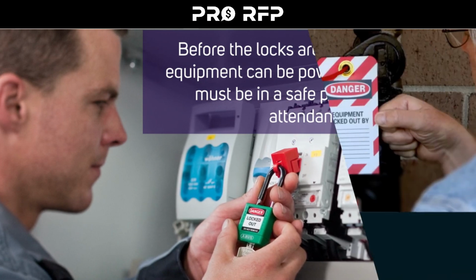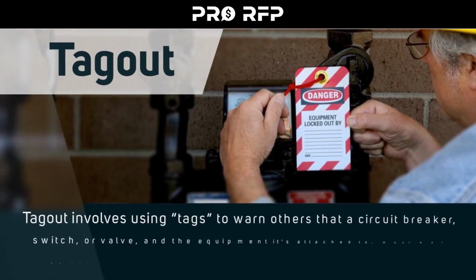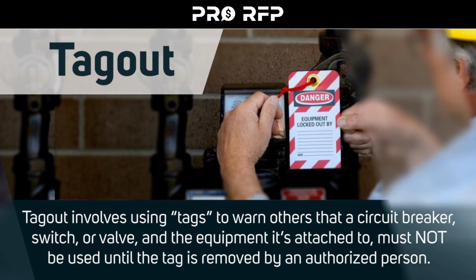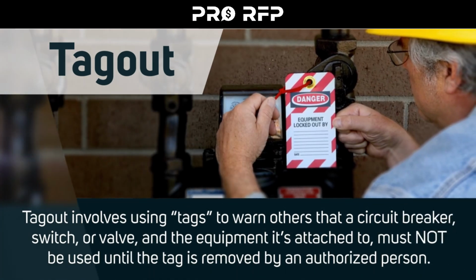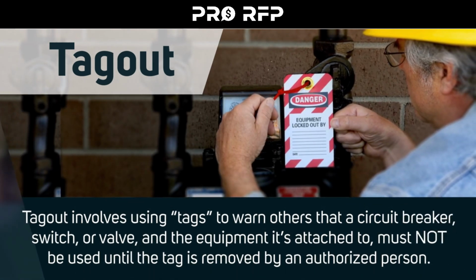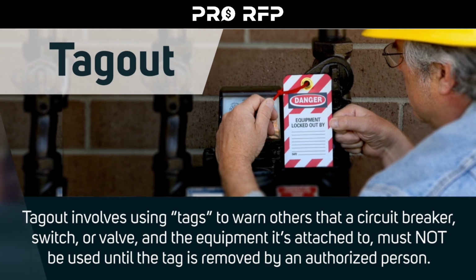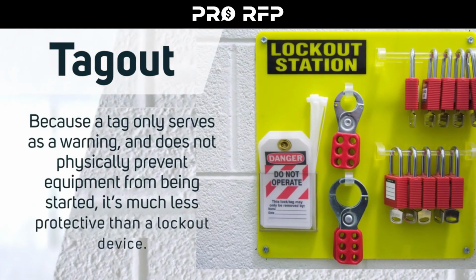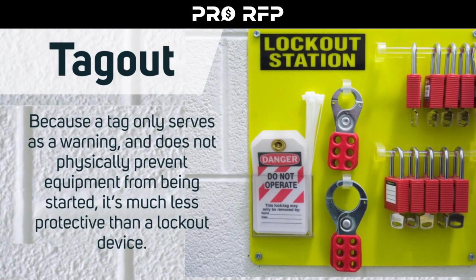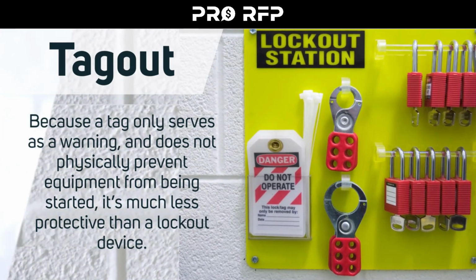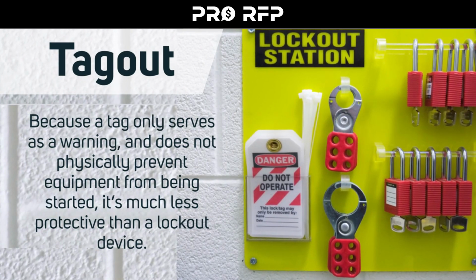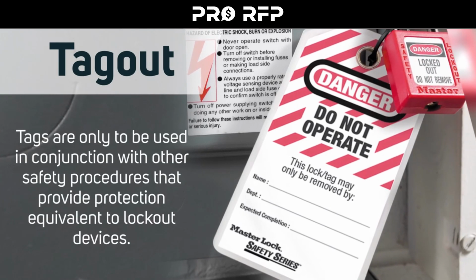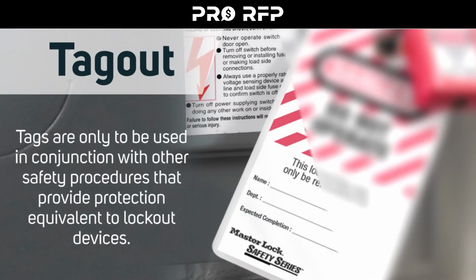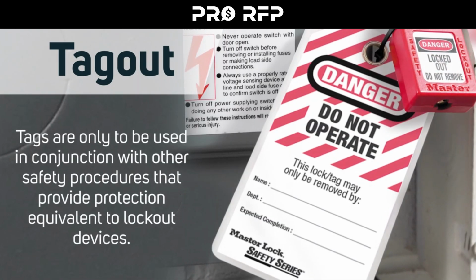Tagout involves using tags to warn others that a circuit breaker, switch, or valve and the equipment it's attached to must not be used until the tag is removed by an authorized person. Because a tag only serves as a warning and does not physically prevent equipment from being started, it's much less protective than a lockout device. Tags are only to be used in conjunction with other safety procedures that provide protection equivalent to lockout devices.